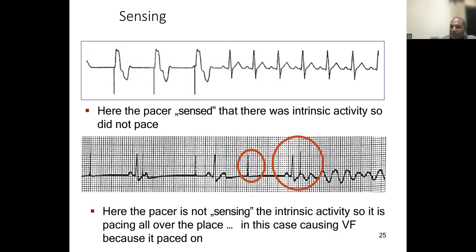In the second strip, you see pacing spikes. You also see some QRS activity. Of course, there's no coordination, and this is what happens. In this red circle, you see the patient's own QRS happened, and on top of the T wave, the pacemaker delivered the current output, and that's not good. It resulted in what is called the R-on-T phenomenon, and therefore a VF. So these things happen. So be careful. Sometimes it may not be a major thing, just a matter of adjusting that sensing button. But this is what happens if it is not appropriate.